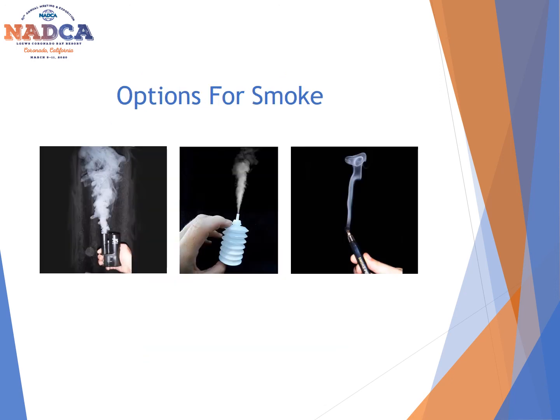So one of the most important things you need to do in order to get buy-in is to have the customer actually see that they actually have duct leakage. And utilizing smoke to do this is one of your best options. So there are a variety of different ways you can do it. You have machines that create smoke. You have little puffers. There's whatever you end up using, but all you have to do is literally create the smoke and then watch how the smoke either reacts, whether it's air being infiltrated into the home or into the building. You can see it moving that way, or you can also see it being sucked out as well.